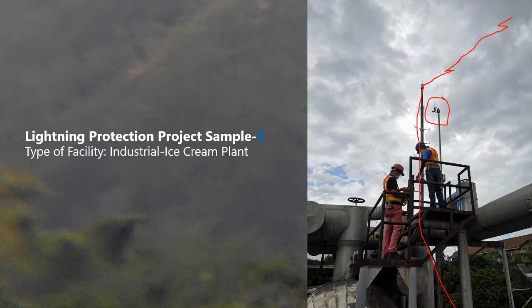The problem is that the step leader, the lightning strike, did not strike our lightning air terminal but struck the structure. The structure hit by the lightning is around 250, almost 200 mm from our air terminal.